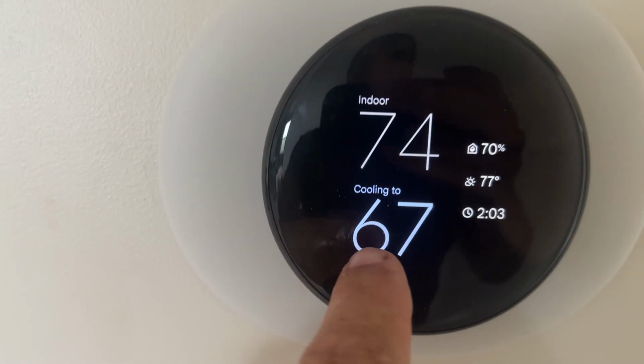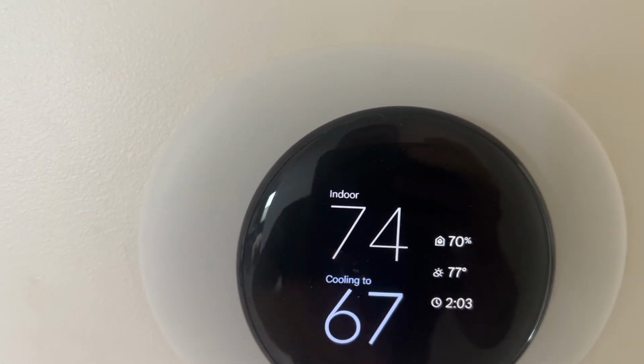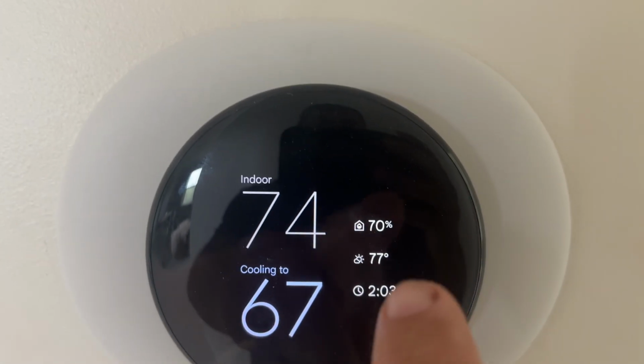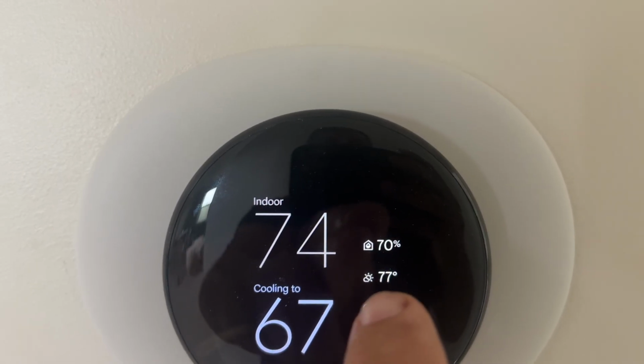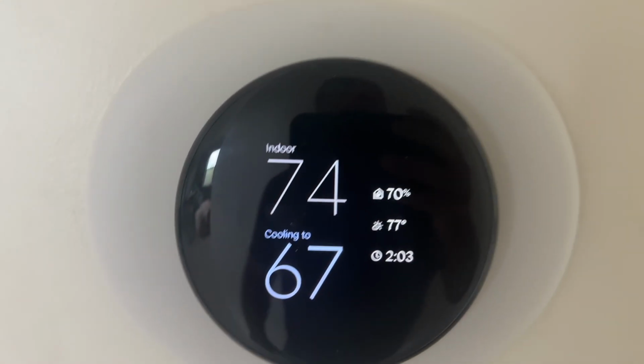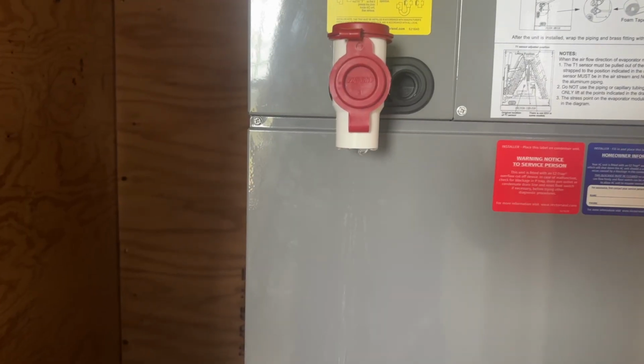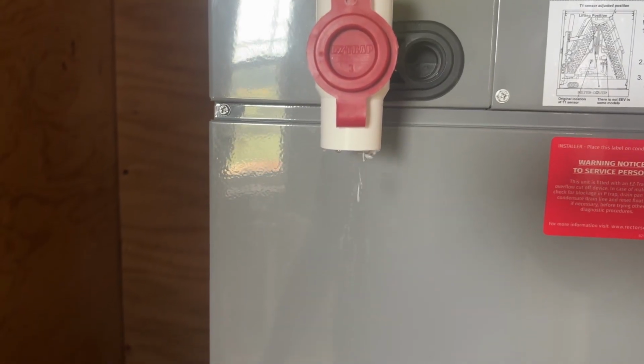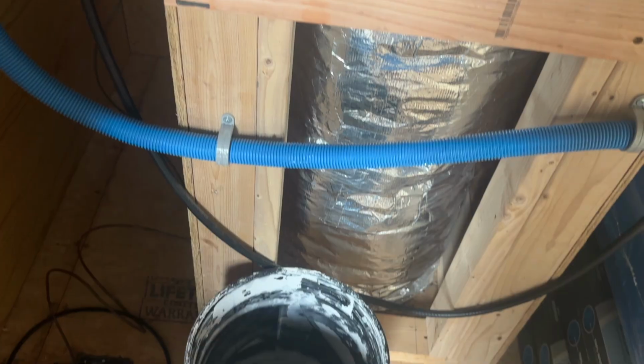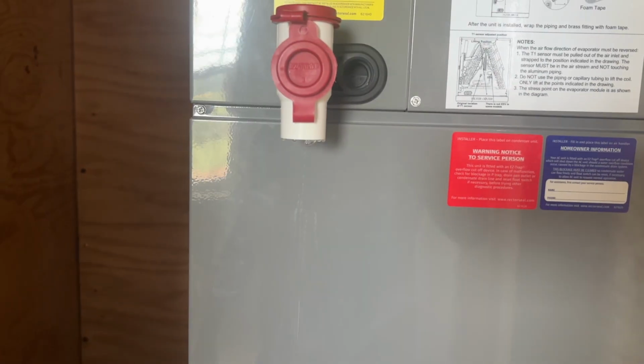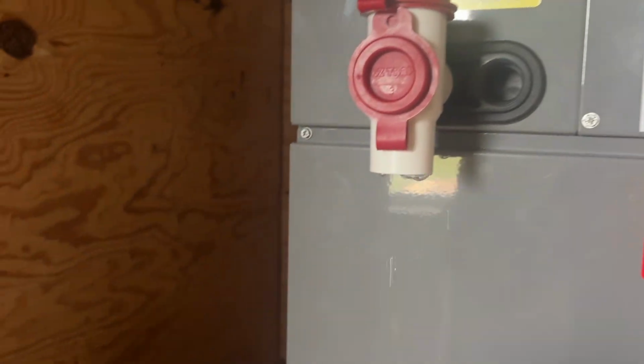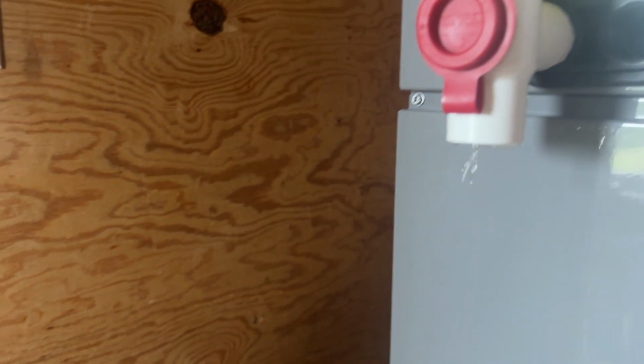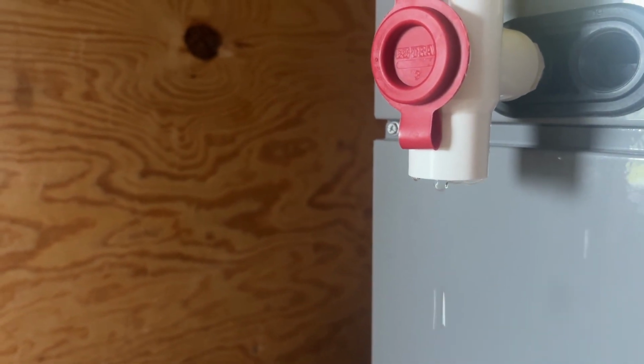We're up to testing the unit now. We have everything hooked up and I'm in the cooling mode on the Nest thermostat, so let's see how it's working. So you can see we have our set point set at 67, it's 74 inside, 70% relative humidity, 77 outside. And after a couple of minutes, we're starting to get water out of the drain pan, which is a good deal. I just have it draining into a bucket for now for testing. You can see how quiet this unit is. That's stage 2 cooling.